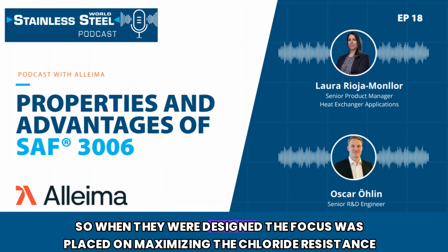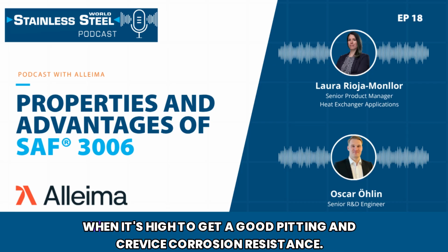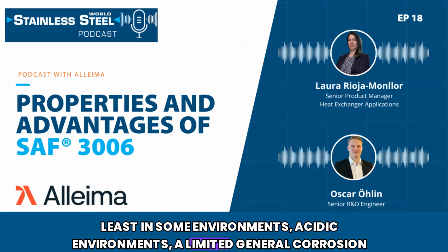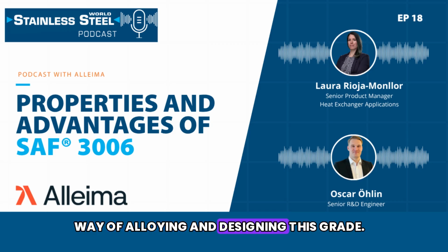When they were designed, the focus was placed on maximizing chloride resistance, and that often means that the PRE, the pitting resistance equivalent, is increased to get good pitting and crevice corrosion resistance. But the drawback can be that since they are optimized for high PRE, they can have, at least in some acidic environments, limited general corrosion resistance. So for 3006, it has been a different way of alloying and designing this grade.